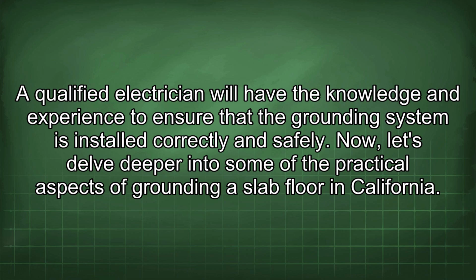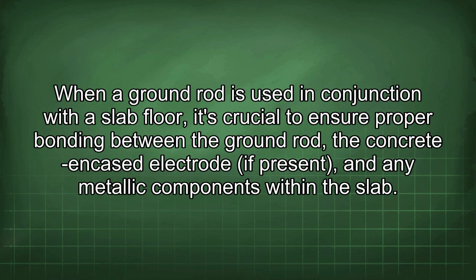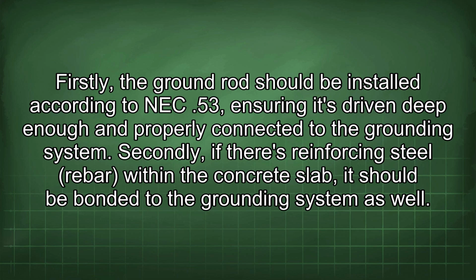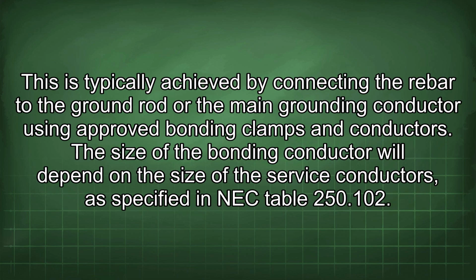Now, let's delve deeper into some of the practical aspects of grounding a slab floor in California. When a ground rod is used in conjunction with a slab floor, it's crucial to ensure proper bonding between the ground rod, the concrete encased electrode present, and any metallic components within the slab. Firstly, the ground rod should be installed according to NEC 53, ensuring it's driven deep enough and properly connected to the grounding system. Secondly, if there's reinforcing steel rebar within the concrete slab, it should be bonded to the grounding system as well. This is typically achieved by connecting the rebar to the ground rod or the main grounding conductor using approved bonding clamps and conductors.